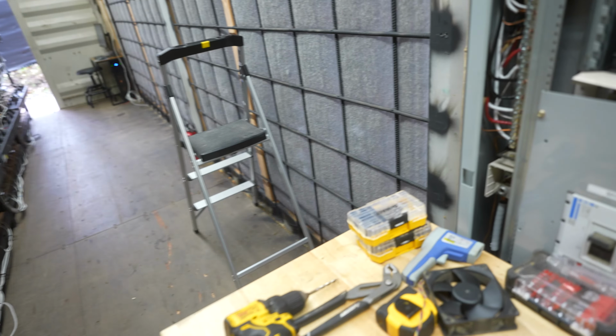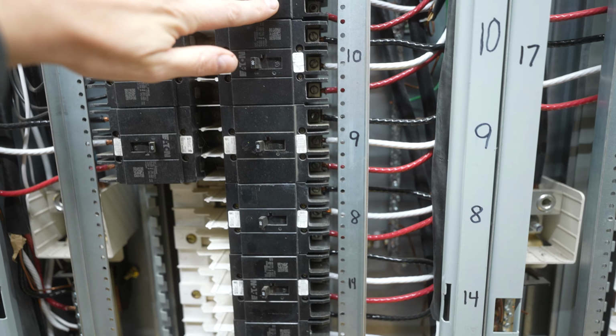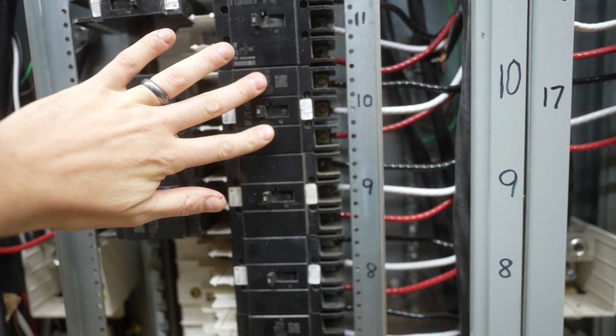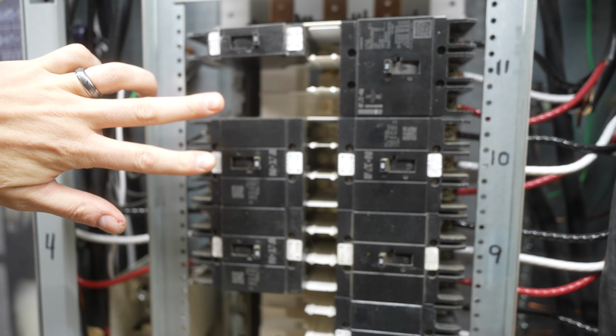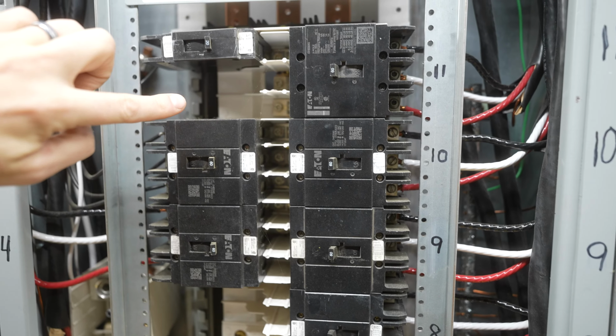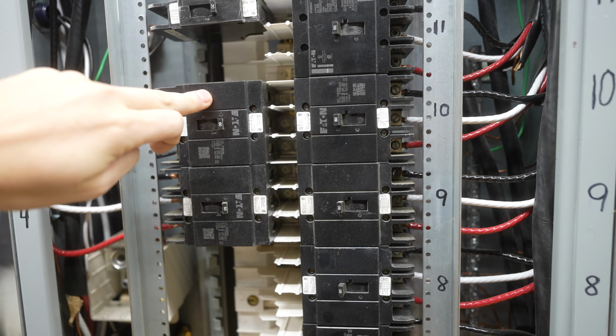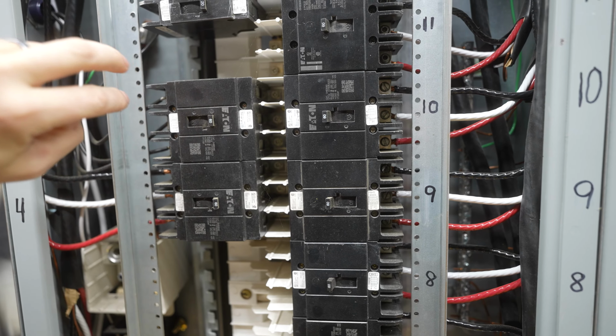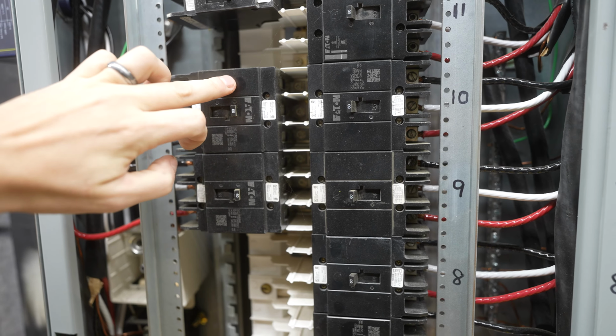The way we set up this container, first of all, we've got these breakers, these PDUs, but we also have them in order here. You see how we didn't mix them around, we didn't just put this breaker right here. You see how we skipped 2 positions and then started this breaker? That's on purpose, so that when we load this one, it's ABC.